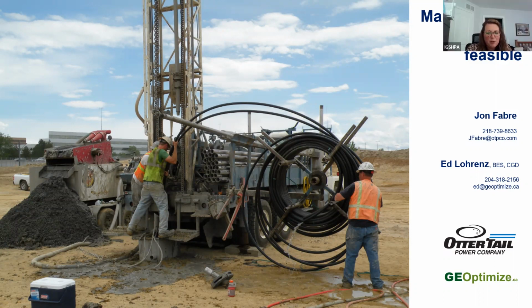Great. Do you know if ground loop software models the hydrological or hydrogeological activity? If so, do you know how to incorporate that in the model if they don't already include that? Certainly the models that use the G function calculations, and that includes Earth Energy Designer, GLHEPro, and part of GLD, take into consideration only conduction of heat through the ground. If there's groundwater flow across the borehole field, or infiltration of rainwater or anything like that, it doesn't model it. The software that uses the peak loads, you can make an adjustment on some of the software that will take into consideration that yes, there is groundwater flow, or no, there isn't. It really doesn't quantify that.